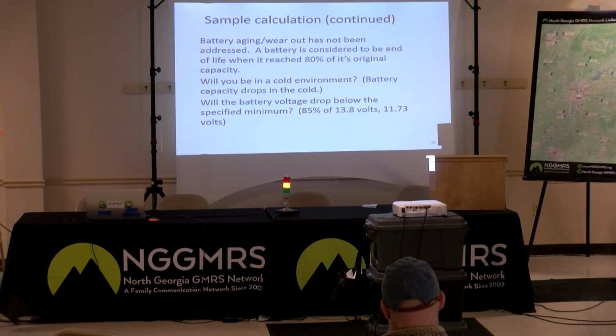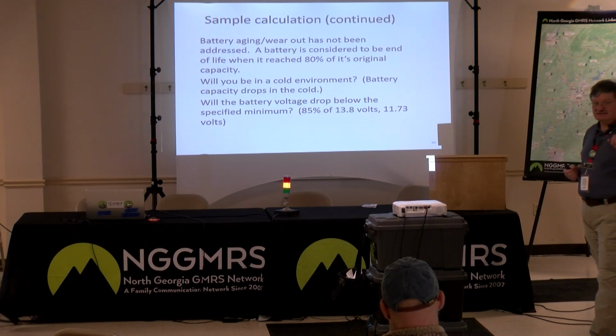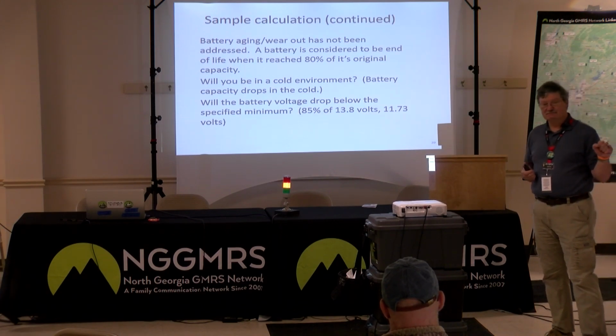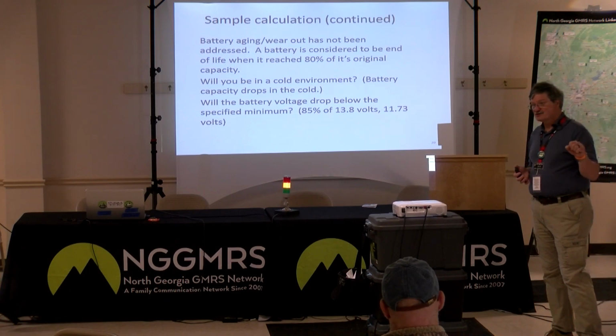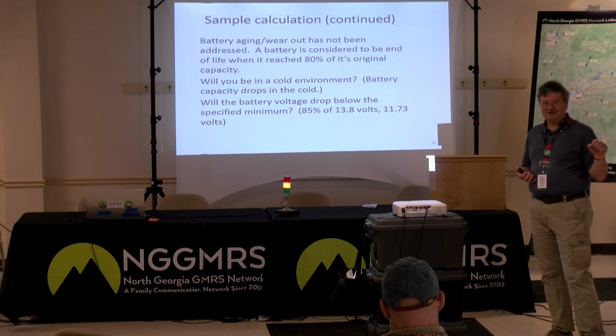The battery aging and wear out has not been considered. When the capacity of a battery drops to 80% of its original capacity, at that point, the battery is considered to be worn out. This is not me. This goes back to IEEE standards, the Institute of Electrical and Electronics Engineers.